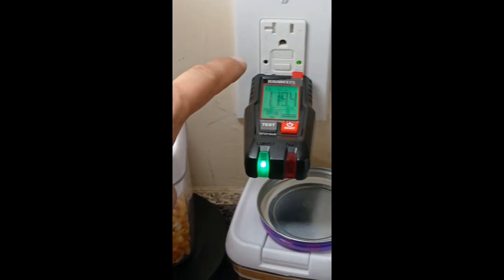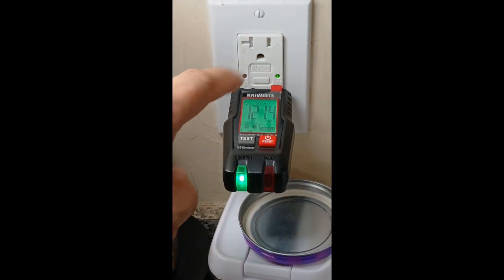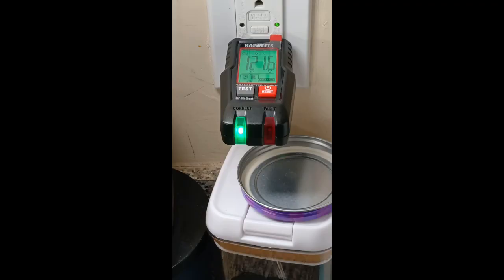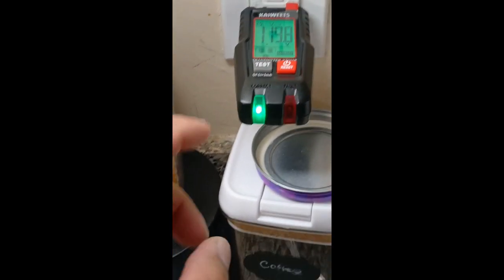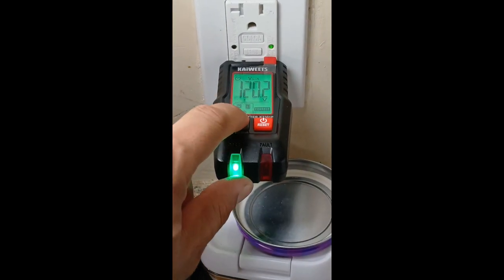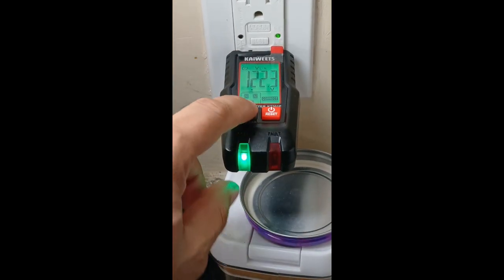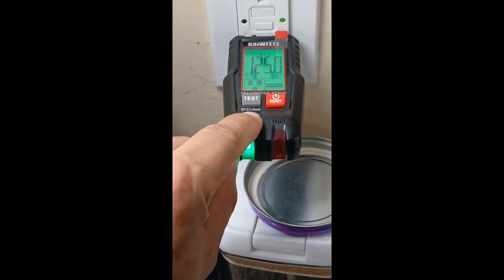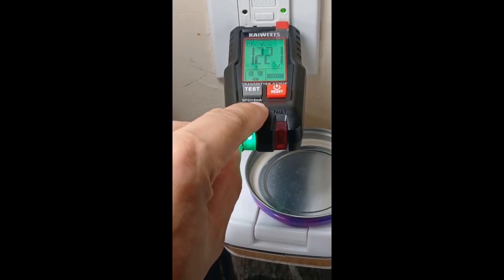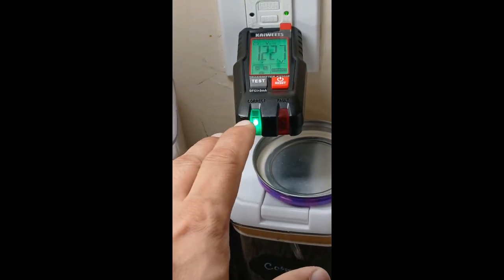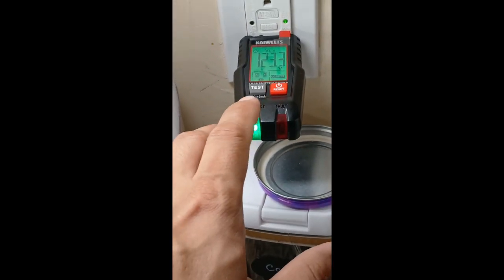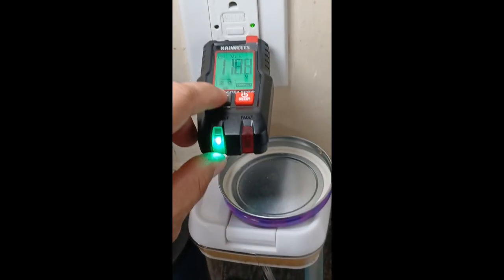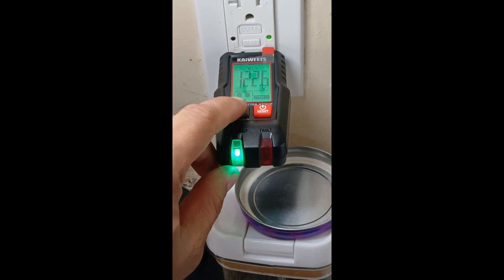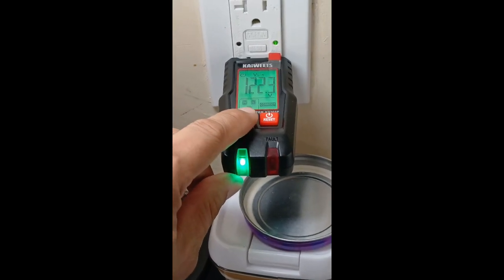You can use this device to check 20 amp and 15 amp GFCI outlets. Really simple. There's a test button that's gray. So let's push that test button. Now, the instructions say you have to hold down the test button, and it's supposed to show a rating of 5 milliamperes. That is the amount of milliamps that this GFCI should be tripping on. All right, so here we go. It's going to simulate a short by me holding down this test button. So here we go.